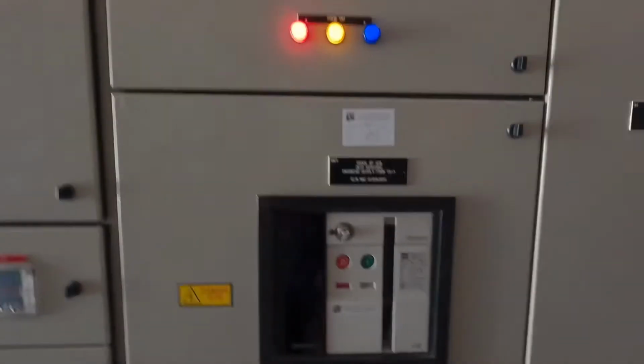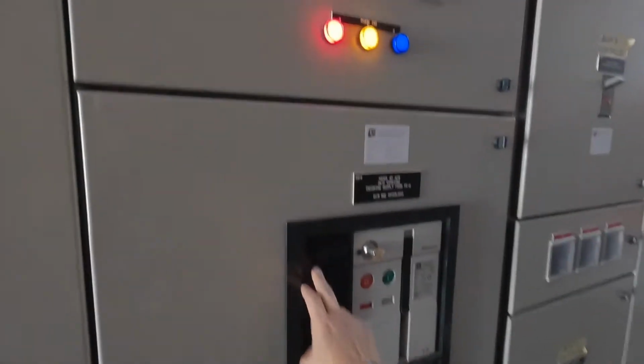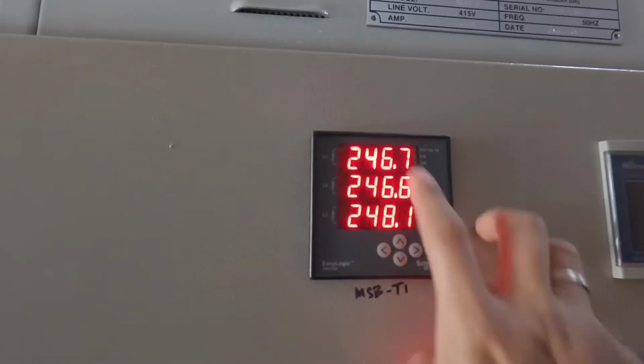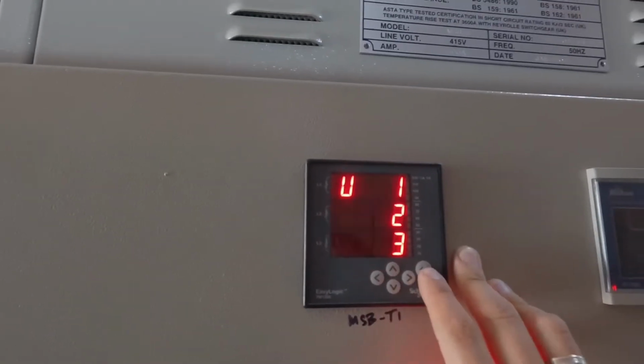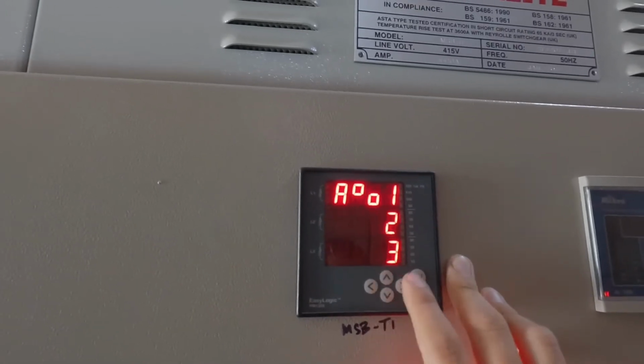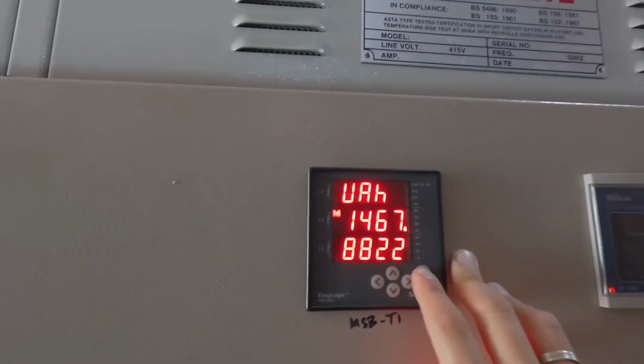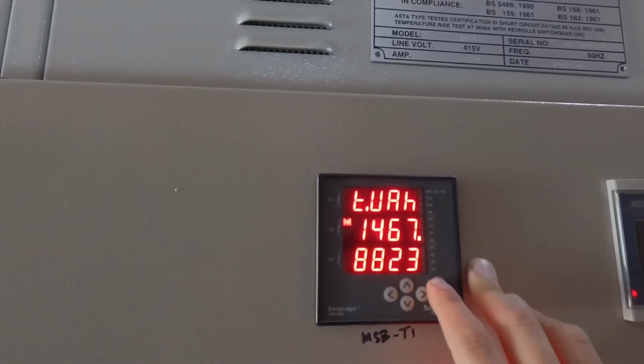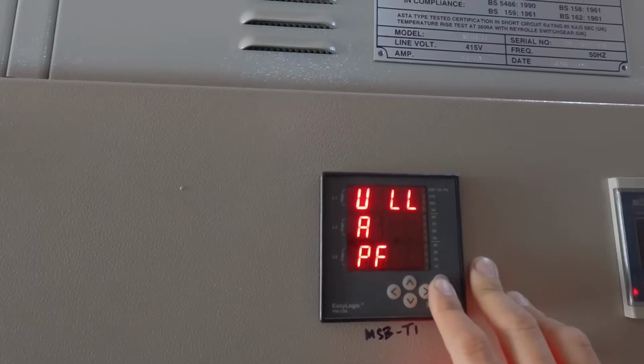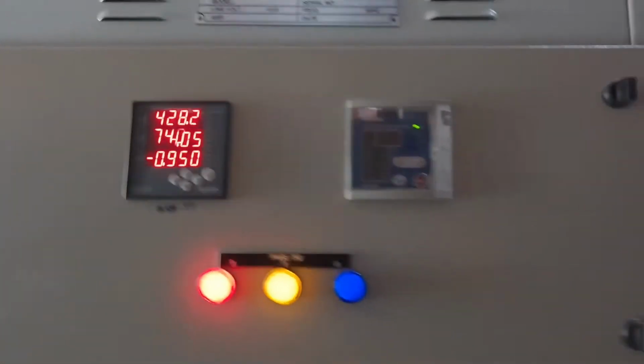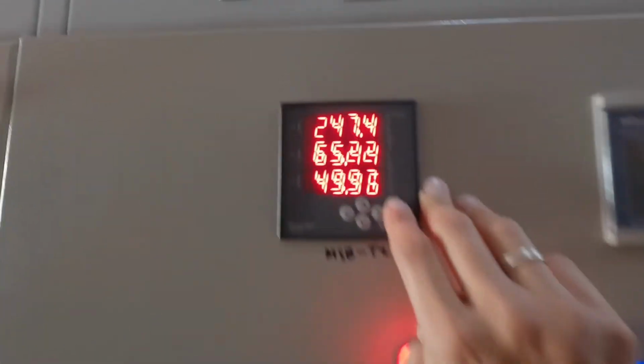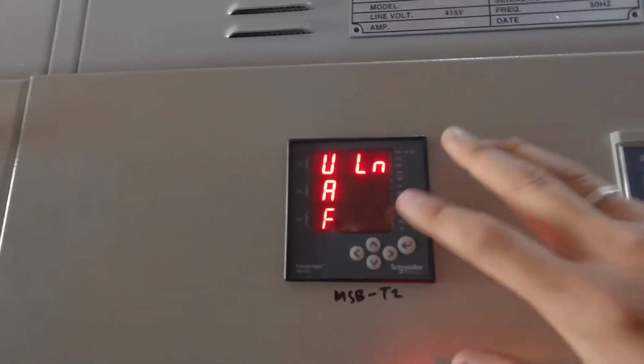Okay, this is the transformer number 1, MSB number 1, and we have the coupler here, and this is the MSB number 2. First of all, let's check the loading for MSB number 1. Okay, voltage is 246, no issue. Okay, let's check the current. 74 amp, and this is MSB number 2. 247 voltage, current is 64 amp, quite low, less than 10%.